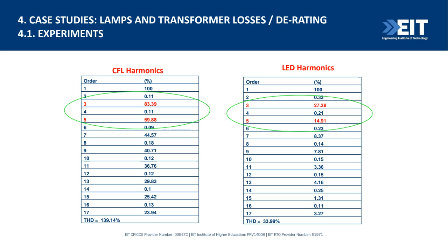If you look at LEDs, it's slightly lower than CFLs, but we still have a third harmonic of about 27% of the fundamental current. The fifth harmonic is about 15%, which is much less than for CFLs. The seventh and ninth harmonics are 8% and 7% of the fundamental current. So CFLs and LEDs both generate harmonics, but CFLs generate much higher harmonics. These are the experimental results from our laboratory experiments. There might be some errors in the percentages presented here, but at the end of the day, the trend is like this.